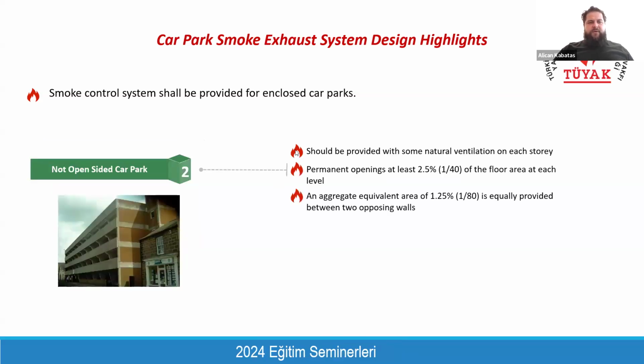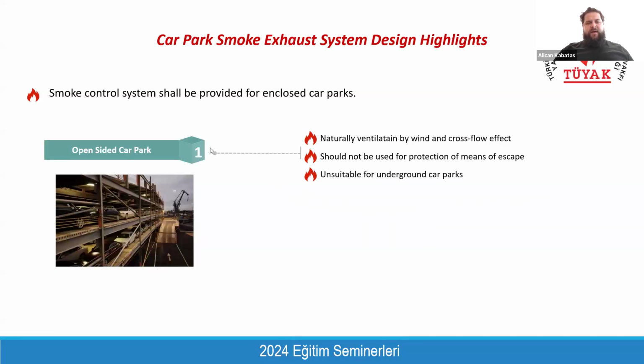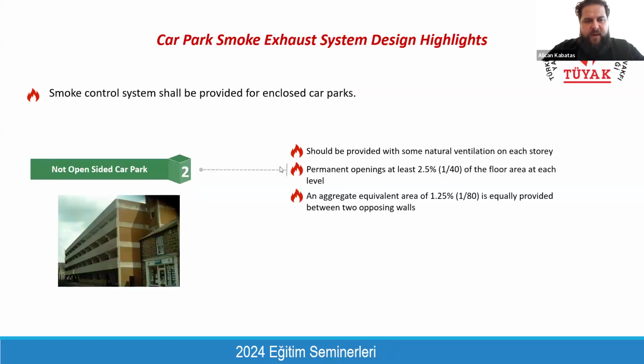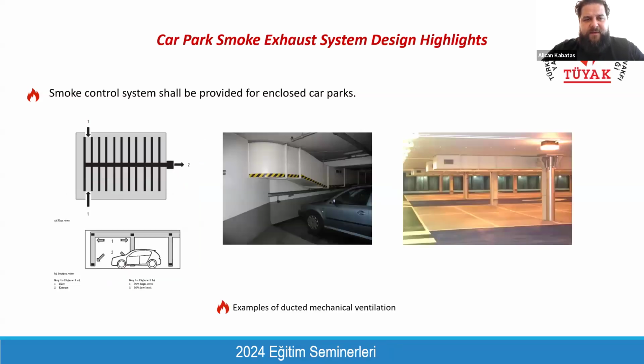But in order to classify a car park as open, at least 5% of the floor area should be provided on the facades. It means the opening on the facades should be not less than 5% of the largest floor area, and at least half of them should be located face to face so that we will have natural ventilation on the floors. And for the enclosed car park, as we stated, we have to provide a smoke extraction system.